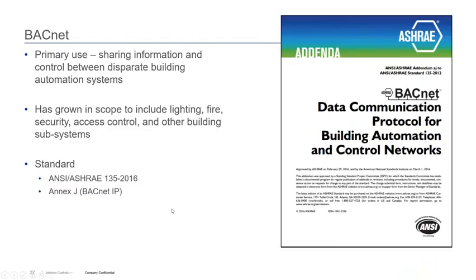So basically, BACnet started off life as a way to share information between your disparate building automation systems. A Honeywell didn't used to talk to a Johnson Controls, which didn't used to talk to a Siemens. BACnet was the answer to that market need. It's grown in scope over the years to include other things like fire systems and lighting, and there's even an access control standard within BACnet, but I believe it's been dropped. No one's been adopting it. The standard is by a standards body, ANSI and ASHRAE both have it as a published standard. And with Secure, we do the BACnet over IP version versus over 2 wires or master slave token passing. We just do the standard BACnet IP.